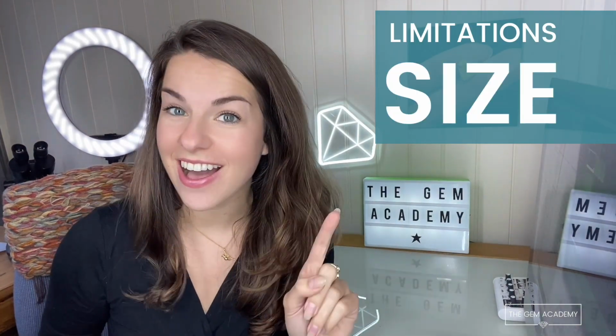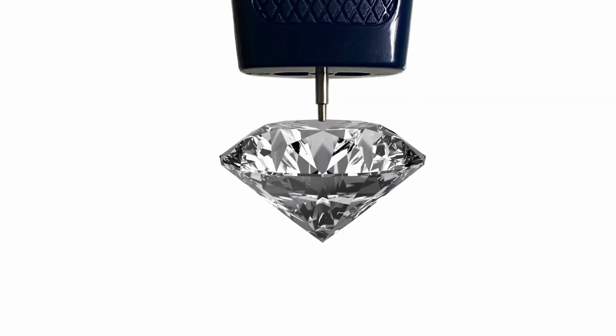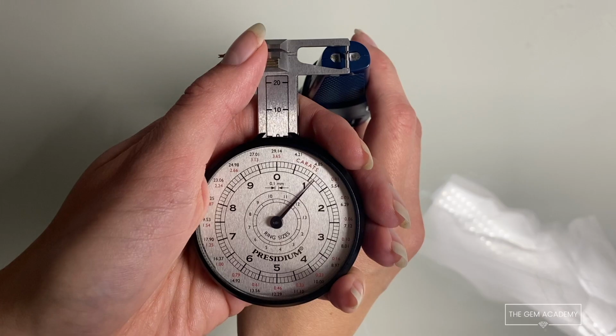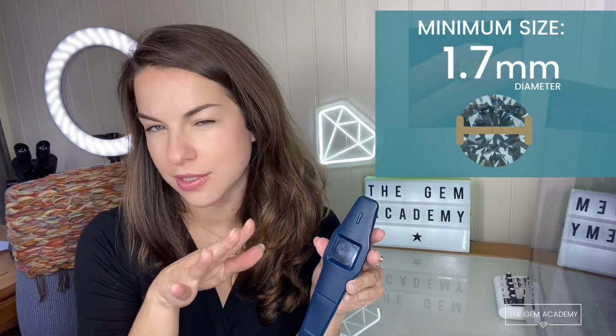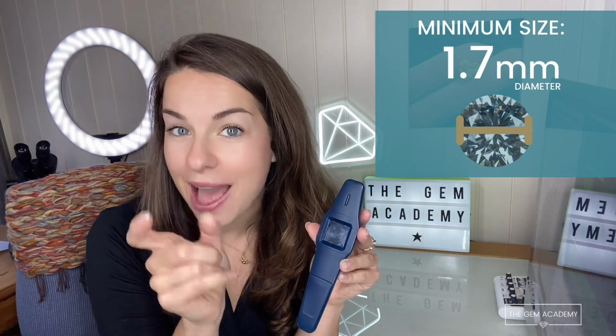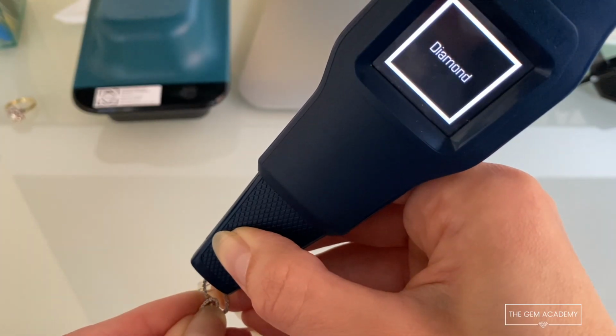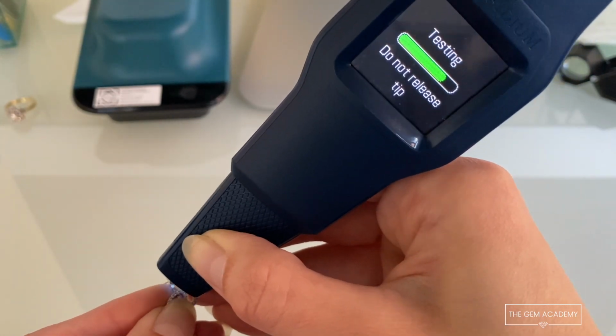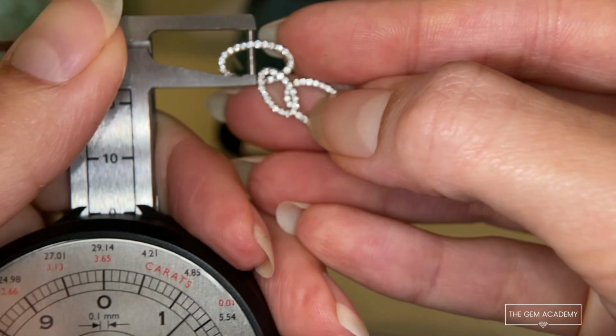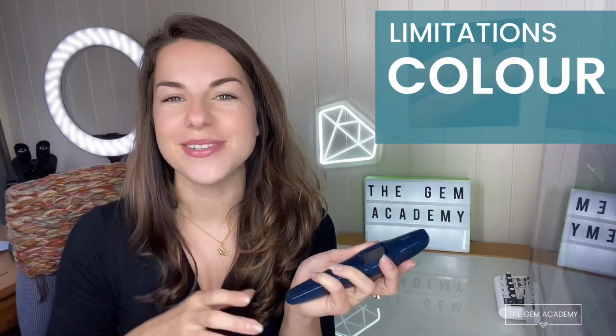Next limitation, size. To get an accurate result, the probe must have full contact with the surface of the stone, which can be problematic for smaller stones. The probe itself measures just over 1 millimeter, so therefore the minimum size stone is approximately 1.7 millimeters in diameter. But this of course depends on the stone's proportion and also its shape. Either way, very small melee may not be accurately tested with this piece of kit. That being said, I did manage to accurately test the diamonds within this earring, even though they measure between 1 and 1.5 millimeters.